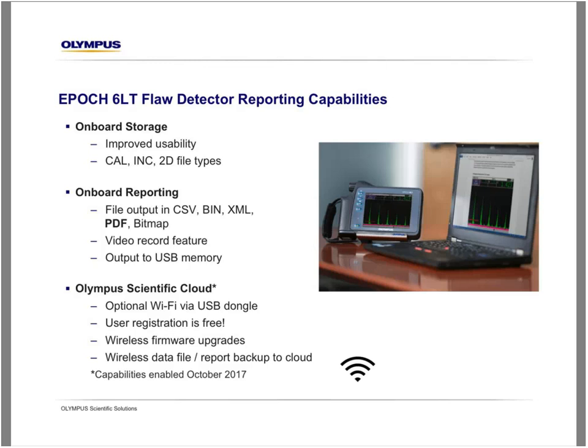We're also featuring onboard creation of PDF reports on the EPOCH 6LT. That allows a protected format report that can come directly off of the instrument onto removable media like a standard USB stick and can be printed and immediately distributed as a summary report of both the A-scan, the waveform that was captured at a particular point within your inspection, as well as the calibration data and thickness readings.